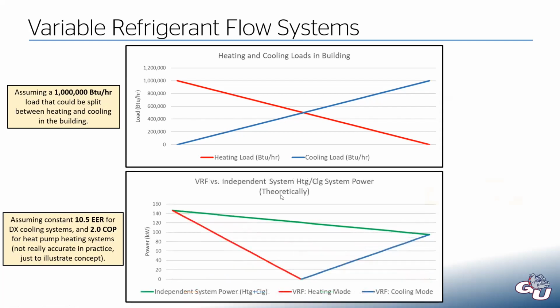But if we had a VRF system where instead at any given point we can share energy between our zones. So if we're on the heating side, peak heating, everything is in heating mode, we still need a lot of heat power really to make that happen. So we haven't really saved much. And then on the other side, if we have this very high cooling load, we need a lot of cooling power. So on each end of this graph, we're not really saving anything as compared to this independent system, but you can see in the middle here where we're going to get a lot of that energy sharing between our heating and our cooling load.